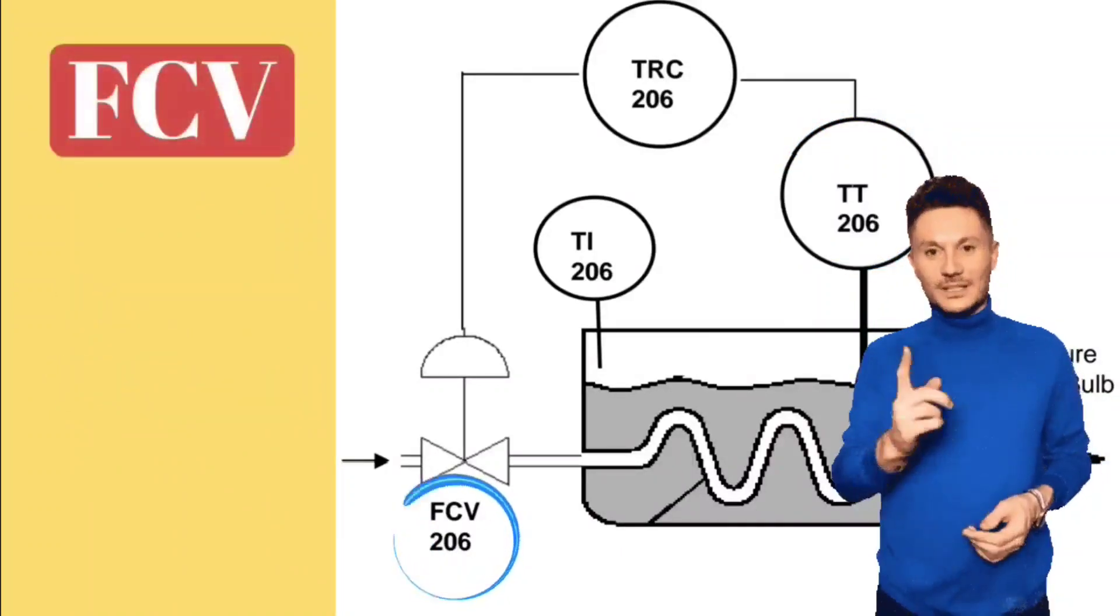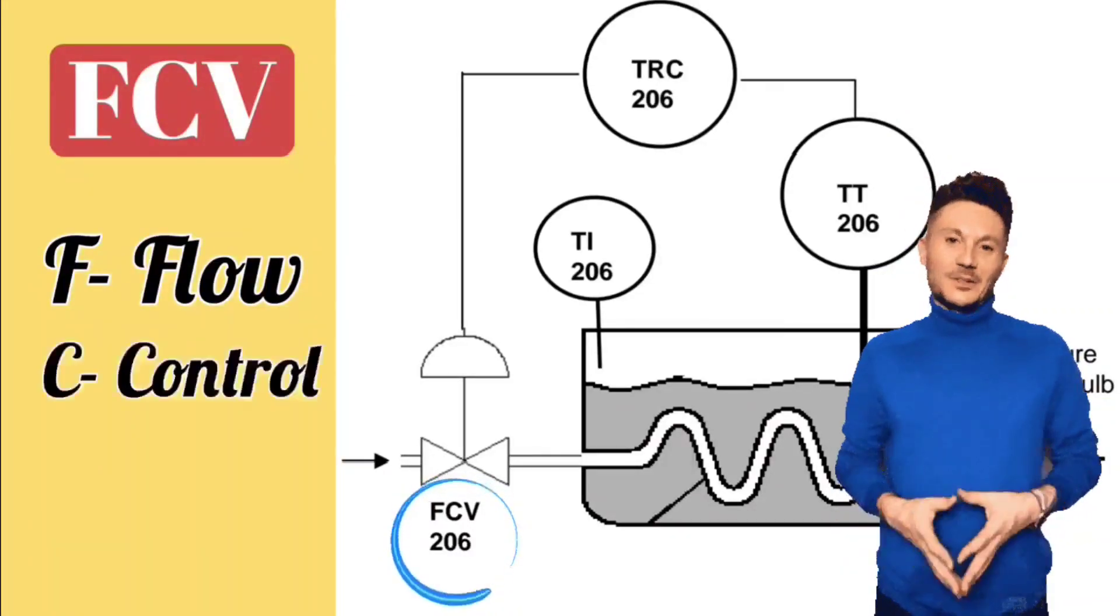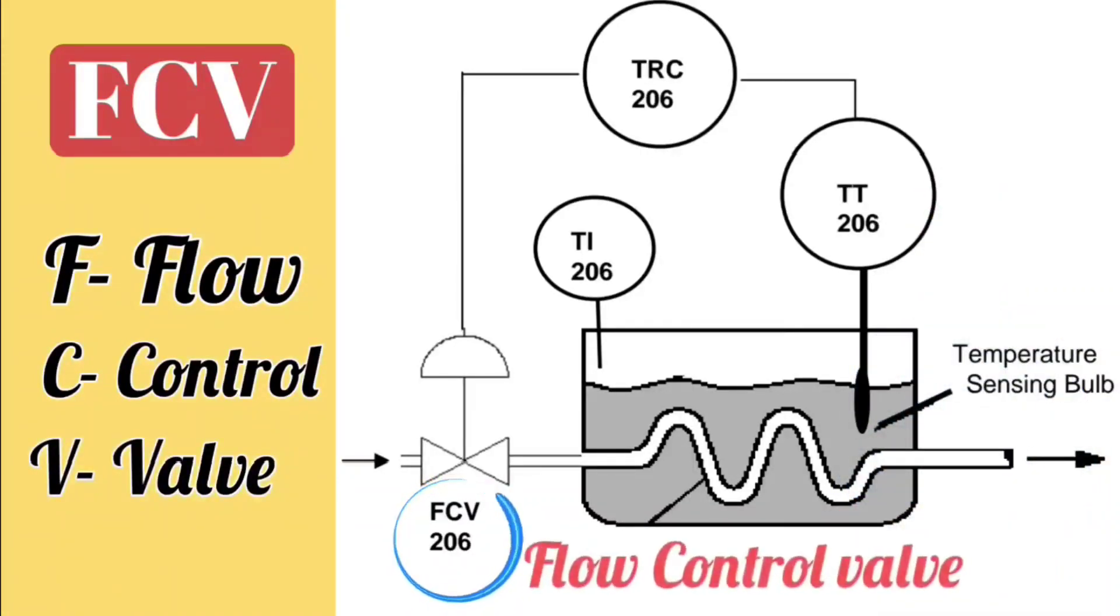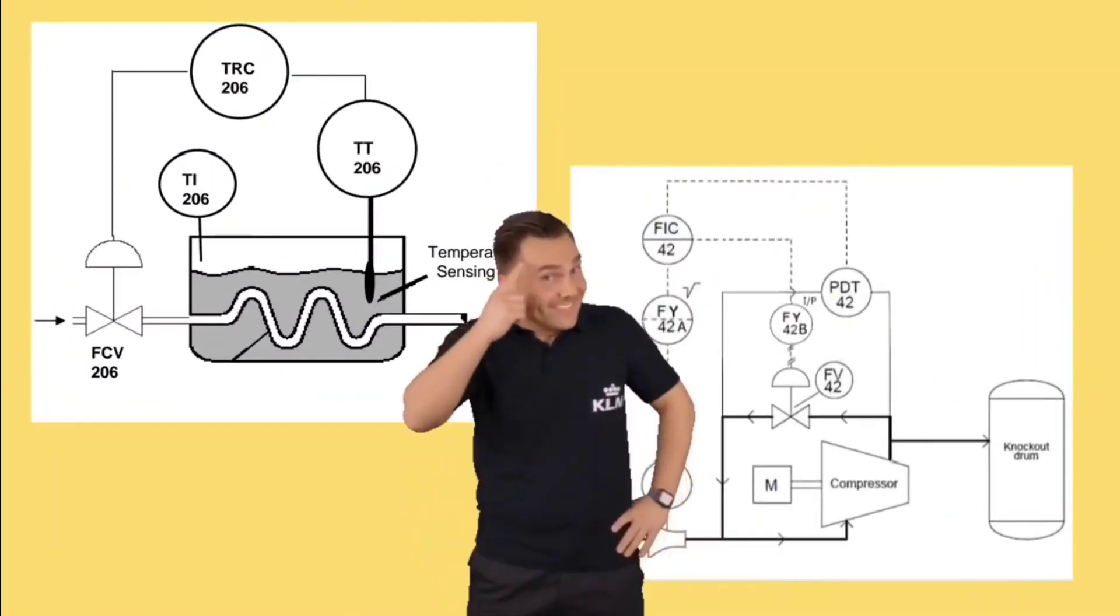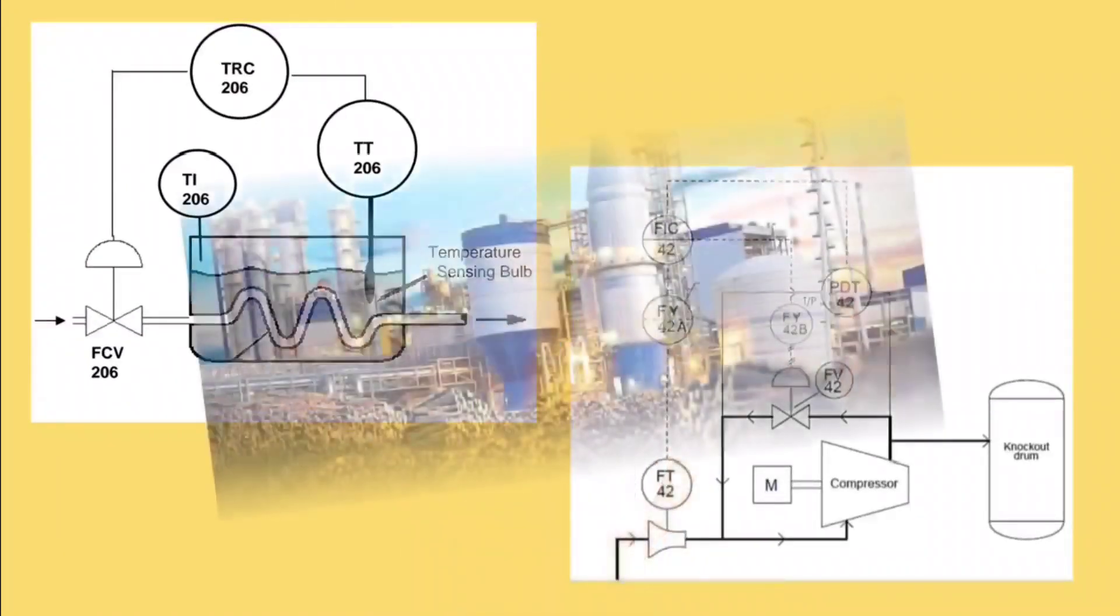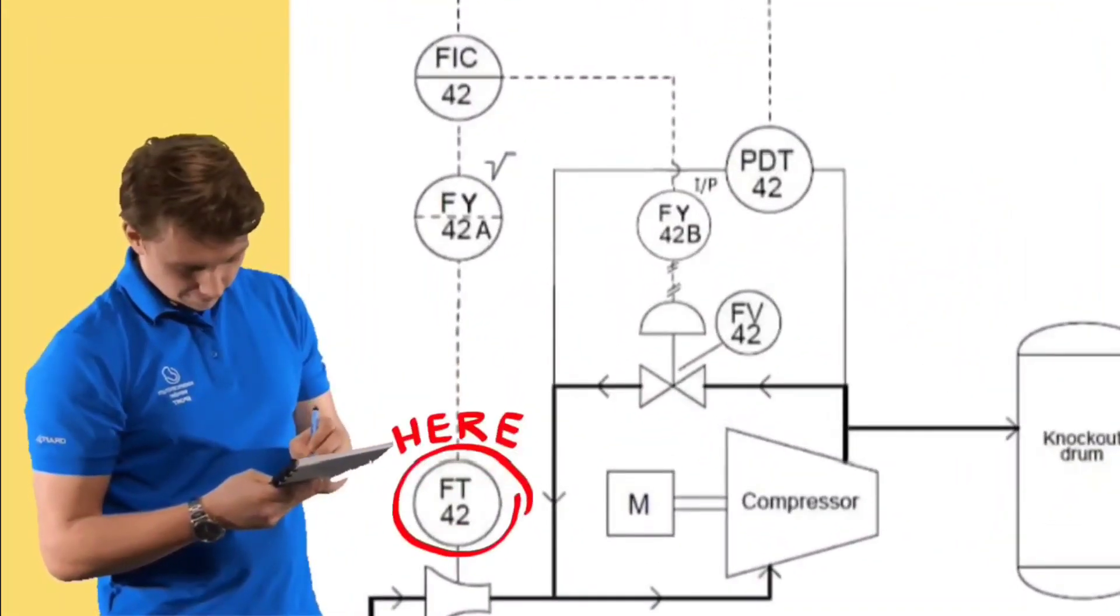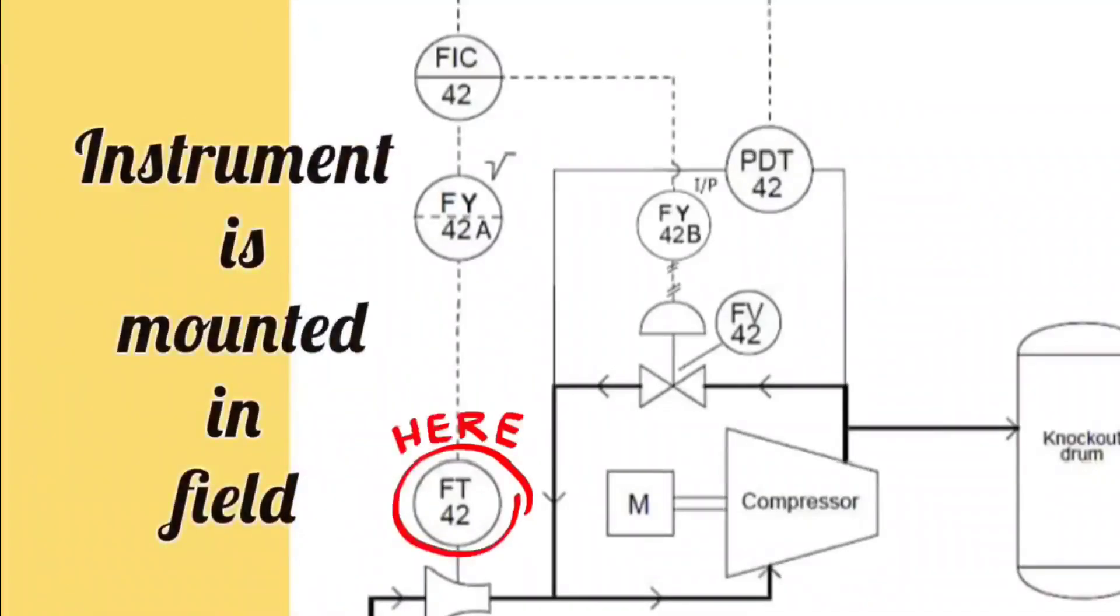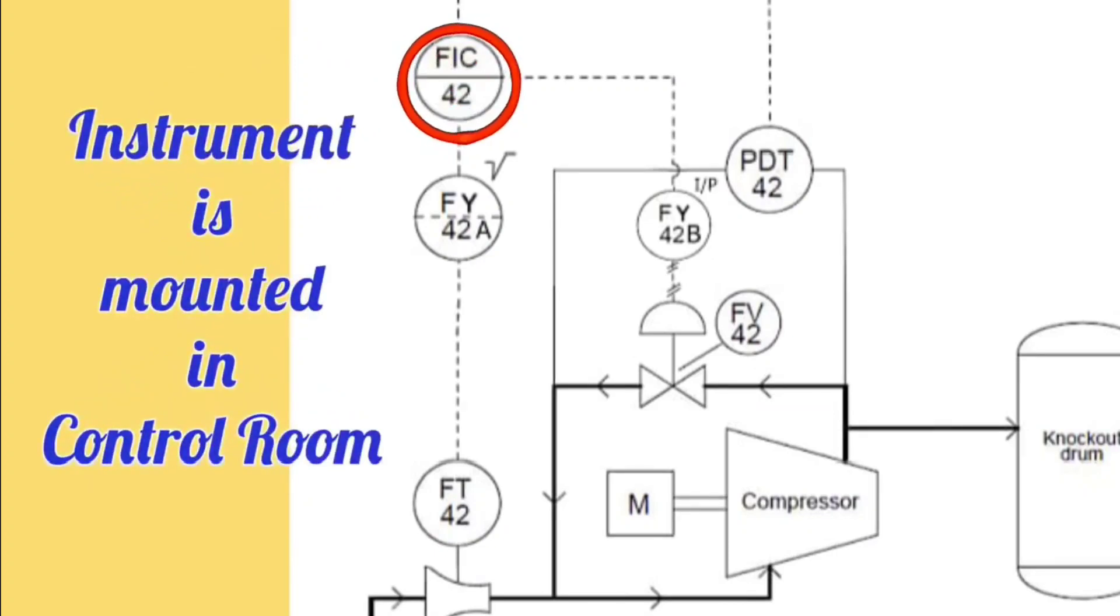Similarly, FCV is written: first letter F means flow, second letter C means control, and third letter V means valve. Means, flow control valve. By looking at P and ID, you will also come to know instruments are connected at which location. Like, if there is no line in between the circle, it means instrument is mounted in the field. If there is solid line in between the circle, it means the instrument is mounted in the control room.